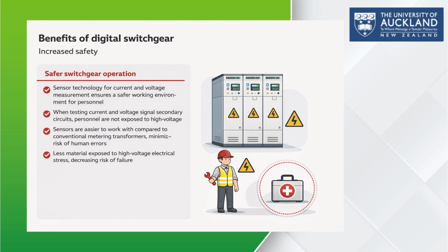One of the biggest advantages of digital switchgear is the significant improvement in safety. Unlike traditional metering transformers, these sensors operate at very low energy levels, meaning the risk to workers is reduced. And when testing or handling secondary circuits, technicians are no longer exposed to high voltage conditions. And because less material is exposed to high voltage electrical stress, the equipment itself experiences fewer failures, contributing to safer long-term operation.